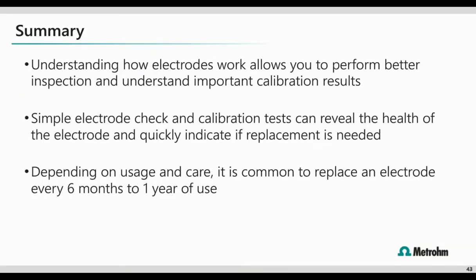And as a summary, understanding how electrodes work always allows you to perform better inspection and understand important calibration results. Simple electrode check and calibration tests can reveal the health of the electrode and quickly indicate if replacement is needed. And finally, depending on usage and care, it's common to replace an electrode every 6 months to 1 year of use.